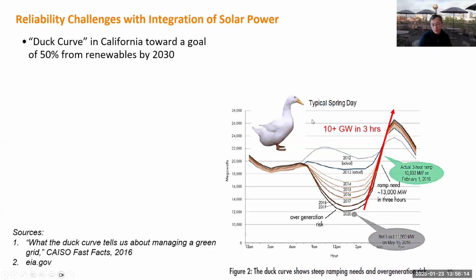This duck curve was generated around 2015 or 2016, based on their load curve from 2012. Then they drew the load curve for 2013 and 2014, and realized that for the curve, especially during the time from probably 7 or 8 a.m. to 6 p.m., the curve would change significantly. That is pretty much the time from sunrise to sunset, when the solar farms start generating electricity.